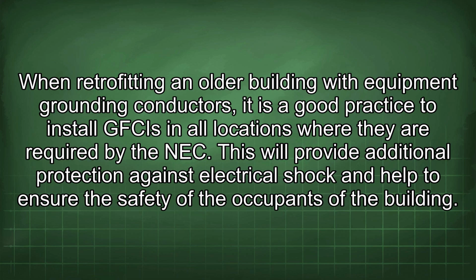When retrofitting an older building with equipment grounding conductors, it is a good practice to install GFCIs in all locations where they are required by the NEC. This will provide additional protection against electrical shock and help to ensure the safety of the occupants of the building.